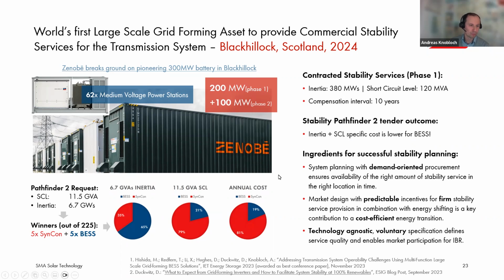But if you compare the annual costs for the provision of the services, we see that the total provision of both services from battery energy storage is much cheaper than from synchronous condensers. And this shows us that inertia and short circuit level specific costs can be lower for battery energy storage. And how to achieve it, this was the learning from this project: system planning should have demand-oriented procurement that ensures availability of the right amount of stability service in the right location and in time.